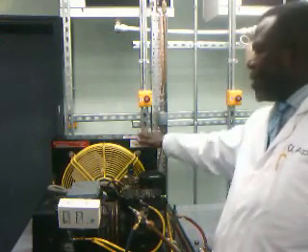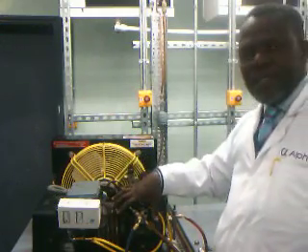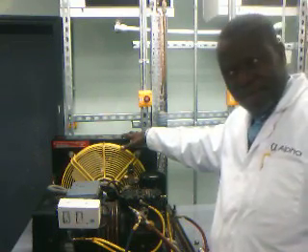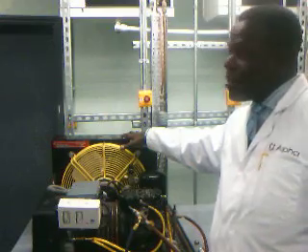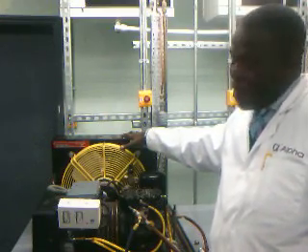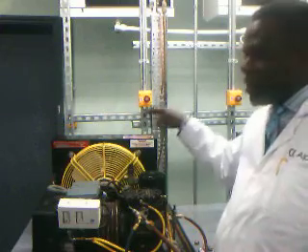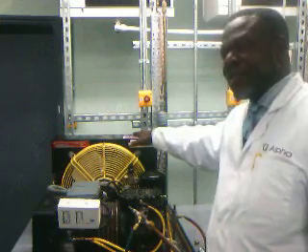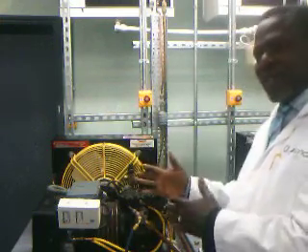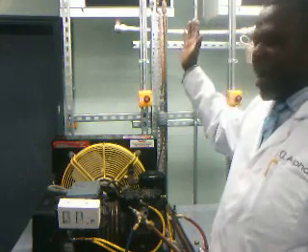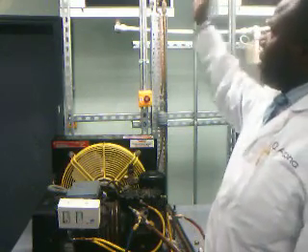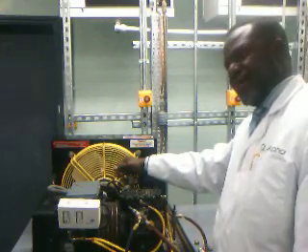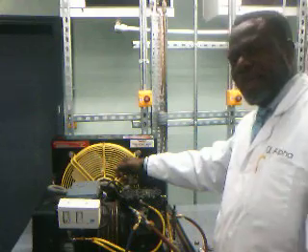You can say if the condenser is bigger than the unit, it will over-condense, so you get high subcooling. And if you don't get any subcooling at all, that is also not good, because that will mean that probably there isn't enough refrigerant. Undercharge, or there is not enough refrigerant going through the condenser. You know the effect it will have on the evaporator. You won't have enough refrigerant going in, and therefore the evaporator will not produce the cooling you want. You won't get the right refrigeration effect, and that in itself is a malfunction.